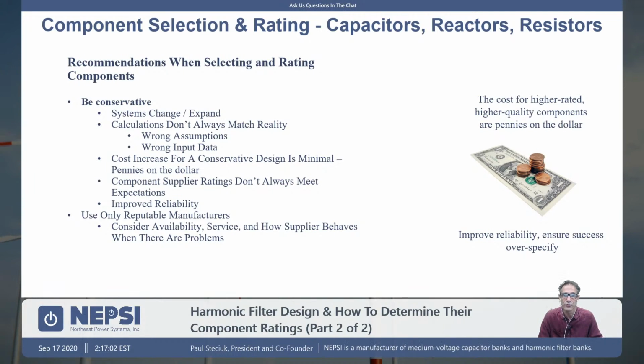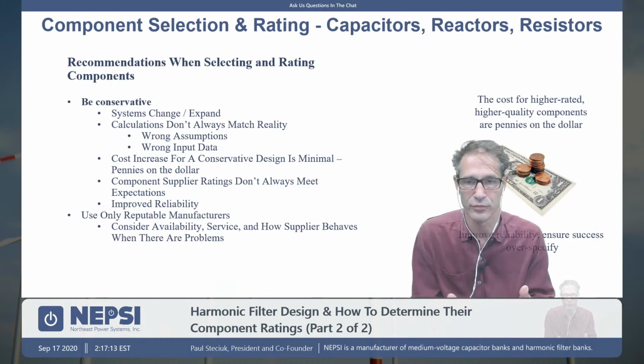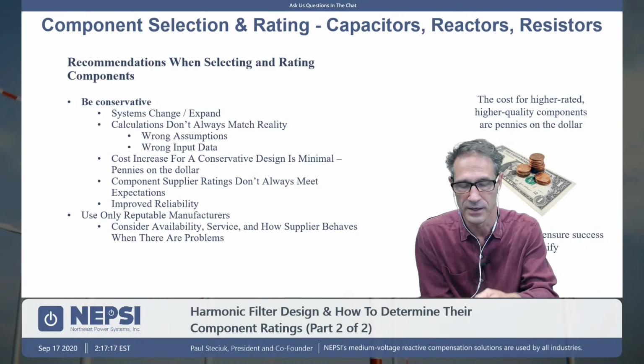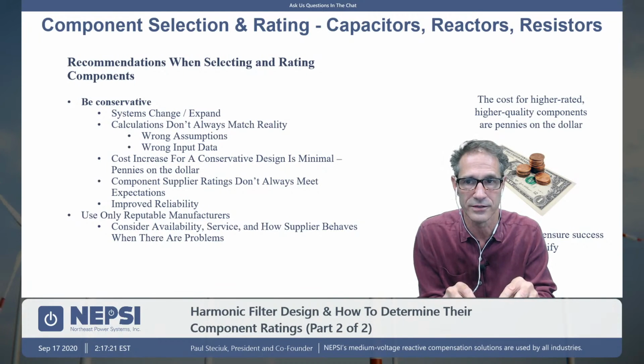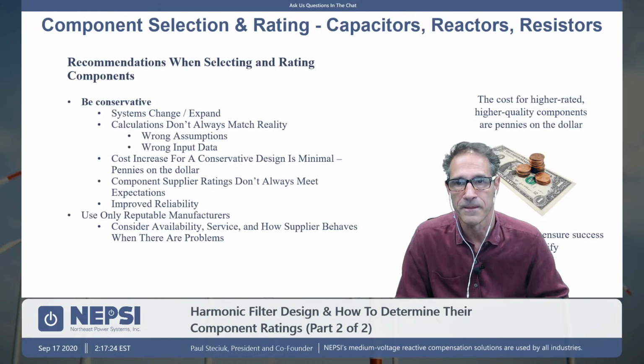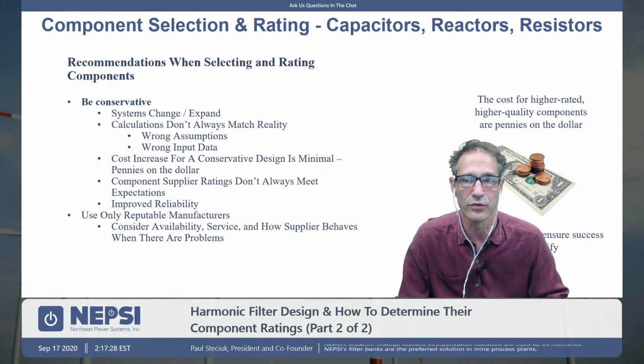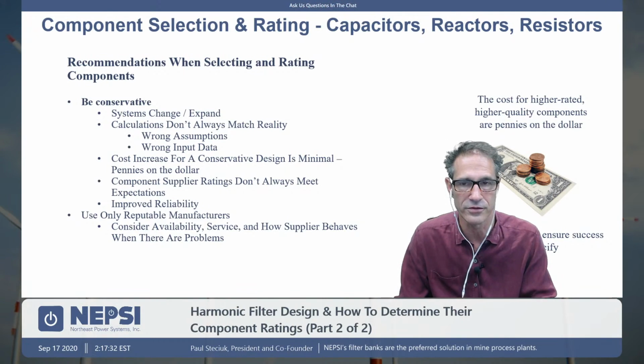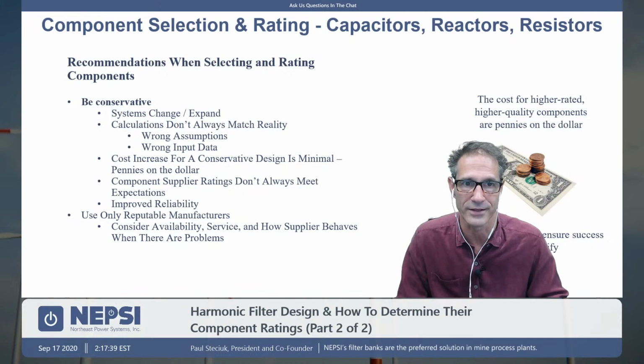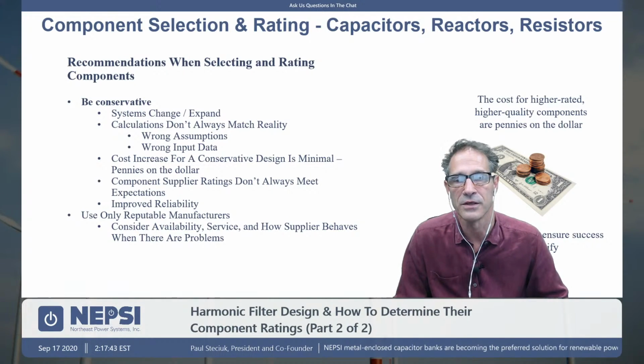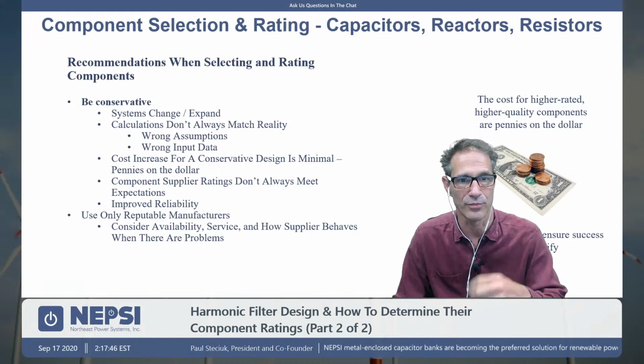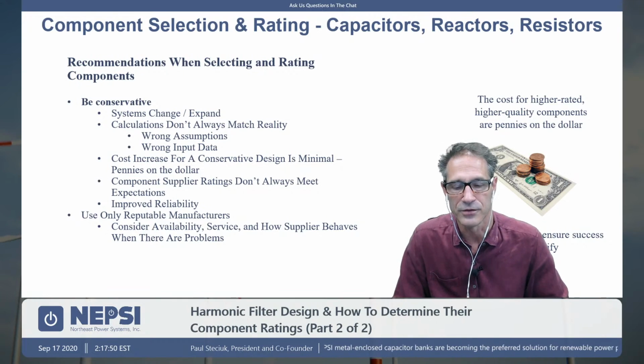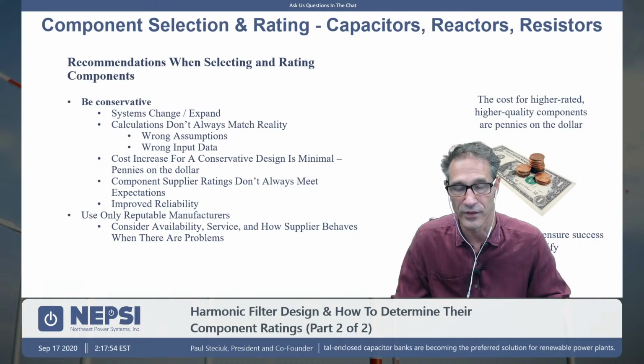We have some recommendations, and the first recommendation when selecting the component ratings is to be very conservative. The reason is that you have a harmonic study, you come up with what you think is the harmonic current flow into the filter, and from there you're choosing components: the reactor ratings, the capacitor ratings, the capacitor voltage rating, and so on. That is based upon simulations, which is kind of an ideal world. We've made assumptions during the simulation process. The question is, are the assumptions all 100% correct? Normally they're not. There are errors in your simulations, and errors in the data that you assumed or that was provided to you by the utility or the drive supplier.